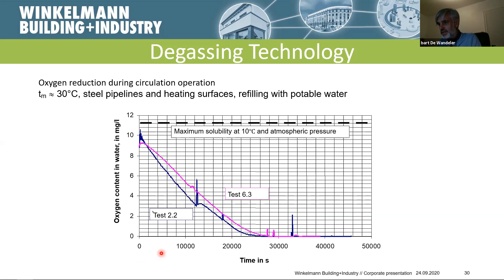The degas systems we have today come in really small sizes, for small systems. I'm talking about systems for 1 cubic meter, 2, 3 cubic meters, and we can also provide standard applications with the control touch. Always the same interface, easy for the engineer, easy for the installer. It's the same interface again, like the Variomat, like the compressor systems, with the same alarms, etc. Those standard systems can also degas about 200 cubic meters, which is already a quite big system, I think, and the pressure can go up to a system pressure standard around 9 bar.